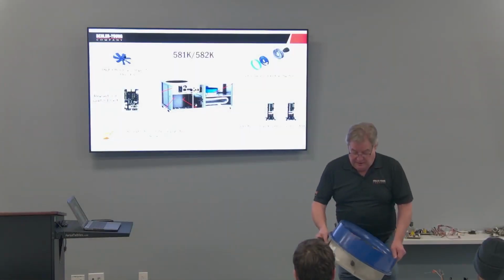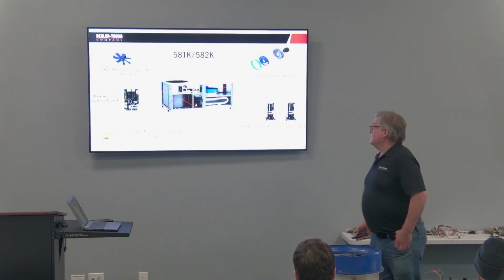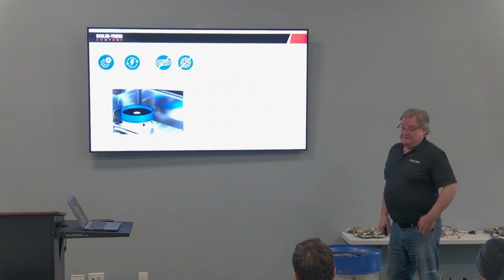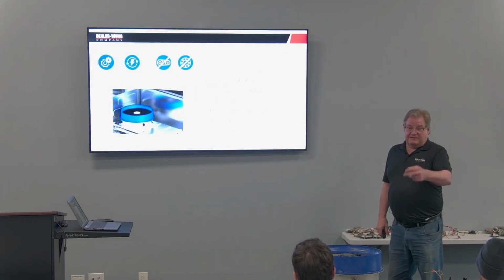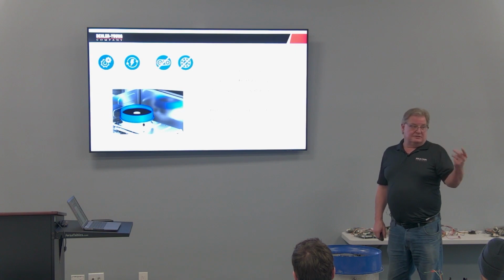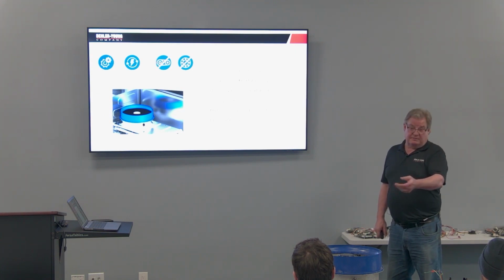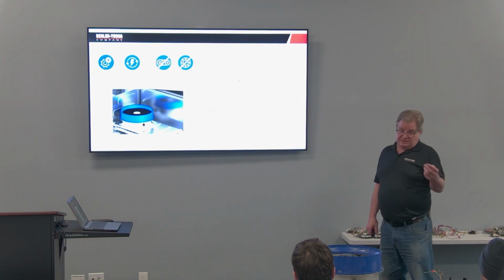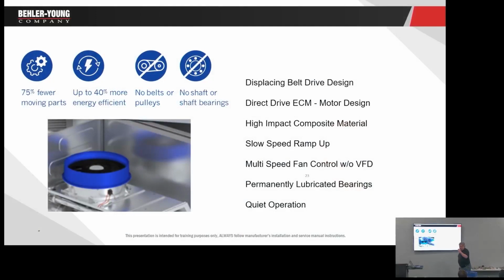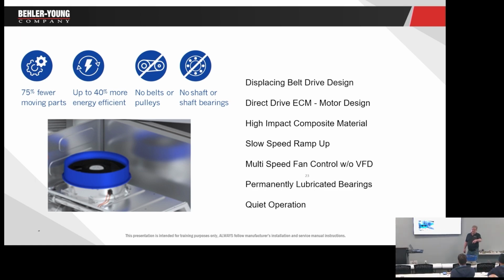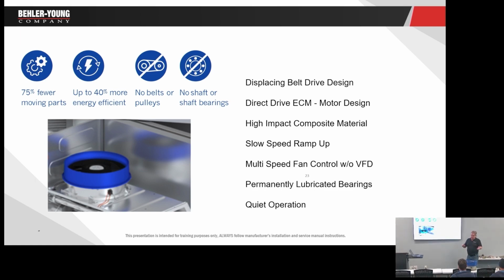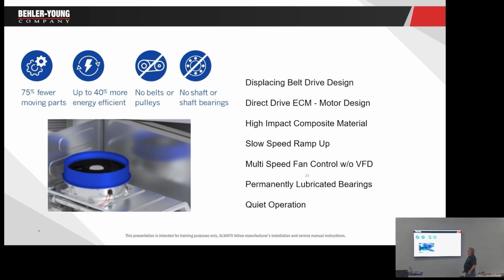One of the reasons they went to that big part is 2-speed, pretty simple to do with an ECM. ECM is way more efficient than a PSC motor, or a 3-phase standard motor. So it all had to do with efficiency. There's no belts. This is really easy to set speed on. We're setting static, we don't have to screw with pulleys. So there's a lot of great benefits to this motor.